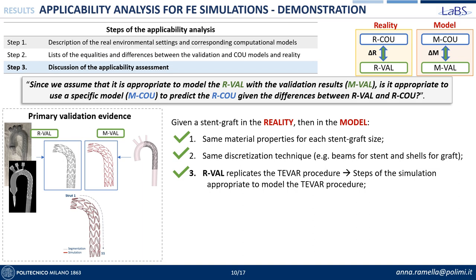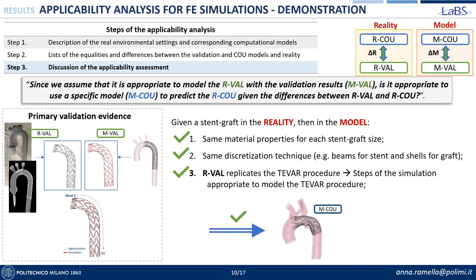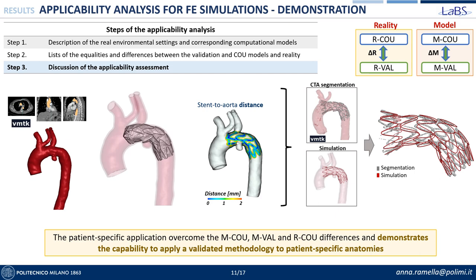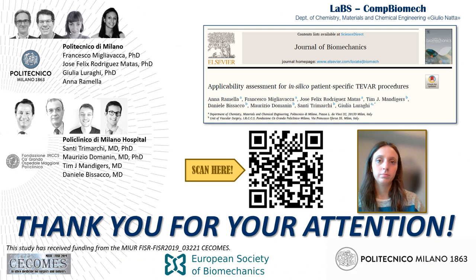Therefore, as in the model of the context of use, we are going to use the same discretization technique for the stent graft and the same material properties and the same steps to replicate the TEVAR procedure. We can also say that this methodology can be applicable to replicate the stent graft implantation into patient-specific anatomy, so replicating a real scenario. As a demonstration of the capability to apply this validated methodology to patient-specific anatomies, we have carried out a pilot patient-specific study comparing the simulation results with postoperative CT image reconstructions, and you see the results in this slide.